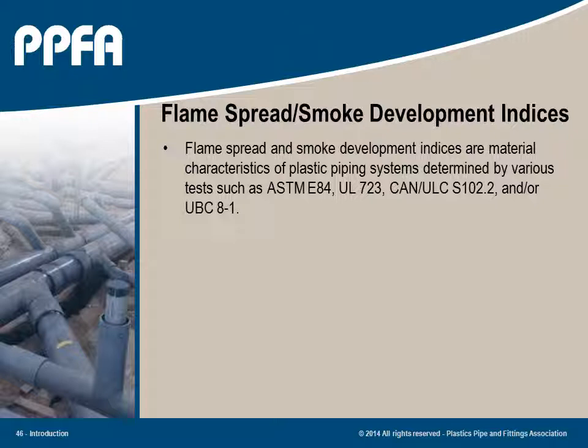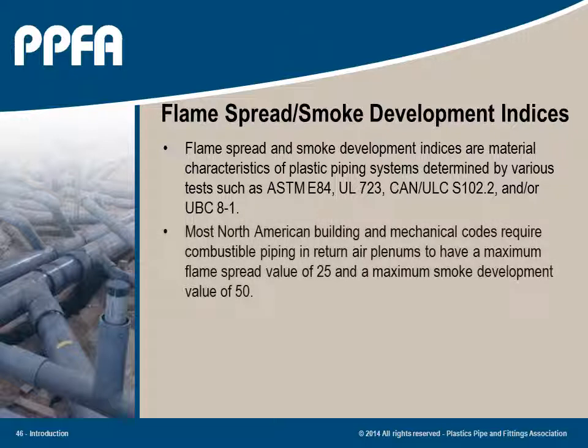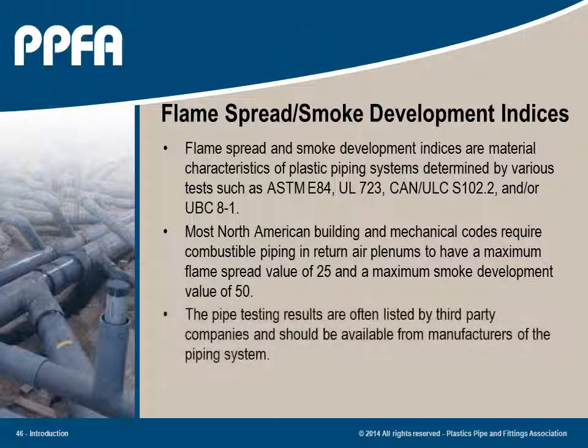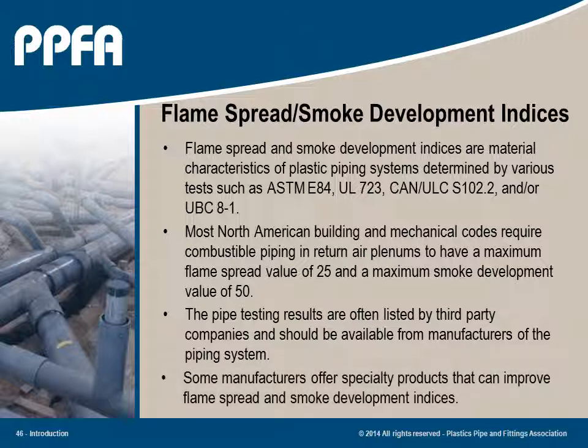Flame spread and smoke development indices are material characteristics of plastic piping systems determined by third-party testing agencies. Most North American building and mechanical codes require combustible piping in return air plenums to have a maximum flame spread value of 25 and a maximum smoke development value of 50. It's advisable to contact plastic piping systems manufacturers to determine the flame spread and smoke indices of their products if used in air plenums. In addition, there are a few companies that offer specialty products that can improve and may meet flame spread and smoke development requirements.